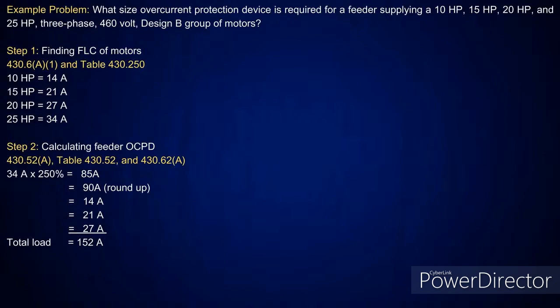So if I go look at table 430.250 and pick up my 460 volt and come down, a 10 horsepower is good for 14 amps. A 15 horsepower is good for 21 amps. A 20 horsepower is good for 27 amps. And a 25 horsepower is good for 34 amps.